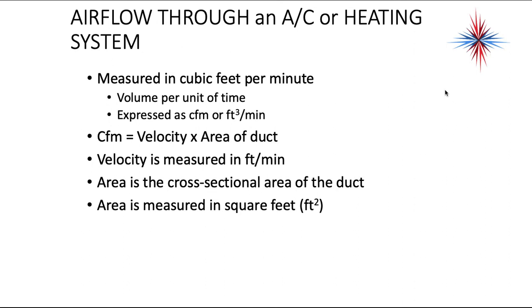Now the CFM is actually a very simple calculation. It's the velocity of the air, that's the speed of the air, times the area of duct that the air is in. So velocity is measured in feet per minute. The area is a cross-sectional area of the duct. Area is measured in square feet.